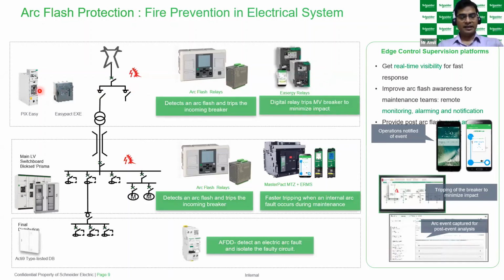And nevertheless, from the MV side, we have a similar kind of solution for the LV network, wherever the LT panel comes. In the LT panel, lots of technology has also arrived, like the IEC 61439 panel, which is very common nowadays. All the hospitals are talking about TTA panels and the most advanced Prisma panel. In the same way, you can also use the arc fault protection relay in your LV network. And whenever we talk about your ACBs, air circuit breakers, or your MCCBs, which are near the load, recently a technology has evolved called ERMS.